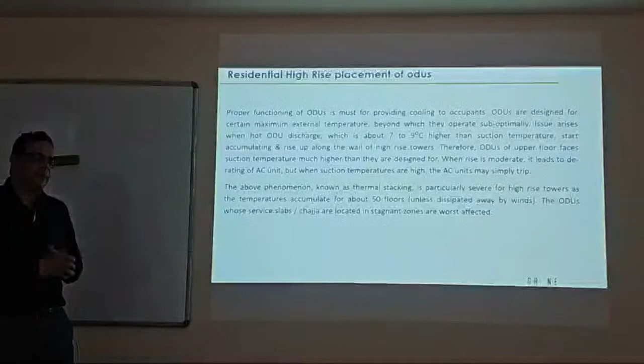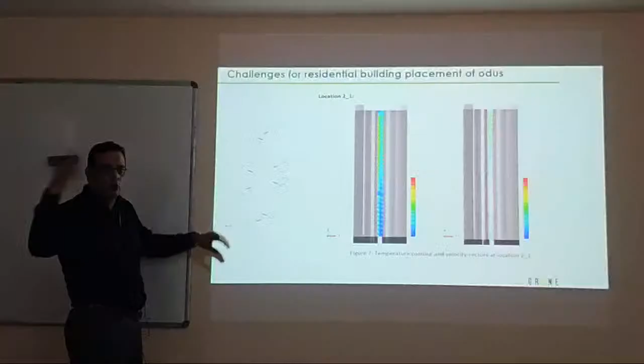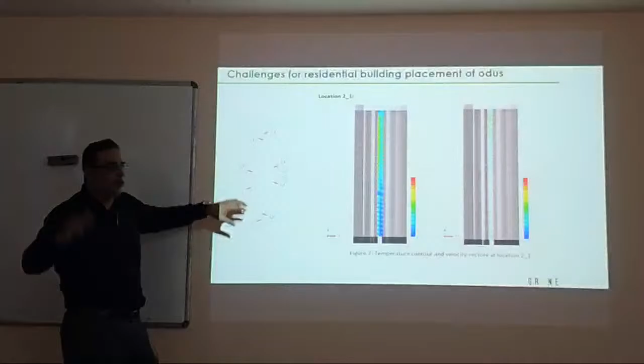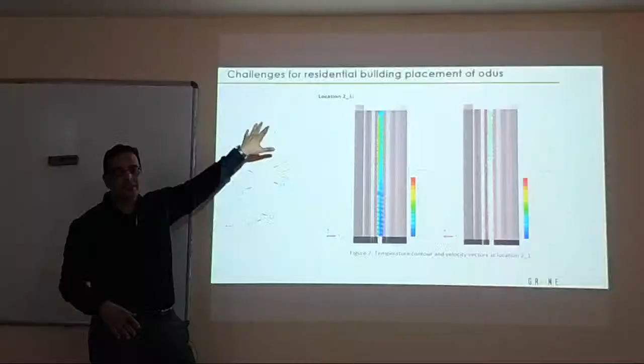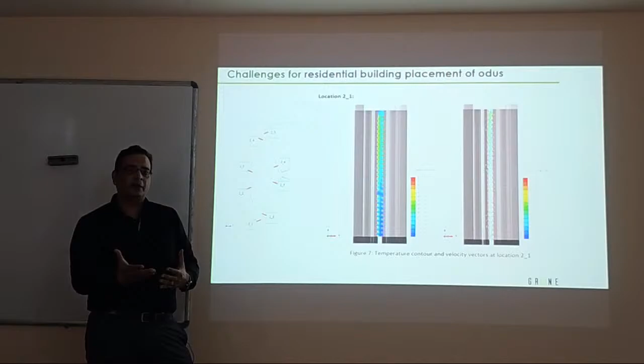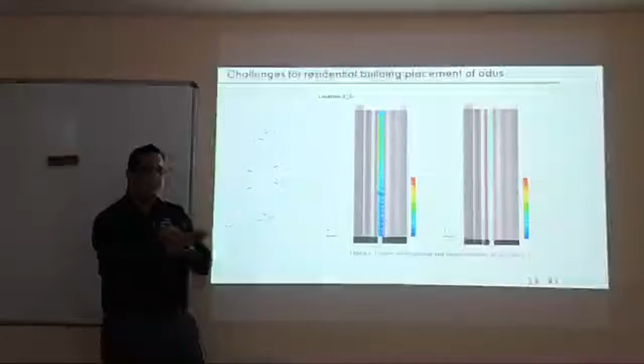The most critical problem lies in the placement of ODUs in high-rise buildings. You may keep ODUs in spaces where there is no air circulation. What happens is the temperatures keep on rising. I'll give you a diagrammatic application. The temperature at the lower level of a tall building is at the general 35-34 degrees outside. Most important, the elevation of the building is required, but it's not the elevation that keeps the building healthy over the years. You need the systems to function. So the placement of the units should not be within a core. And then you find issues related to heavy temperatures coming outside, and these are CFDs that you do on the project to understand the placement of the units particularly.